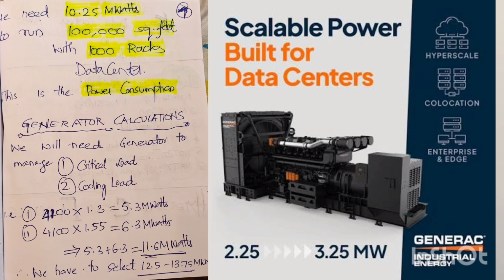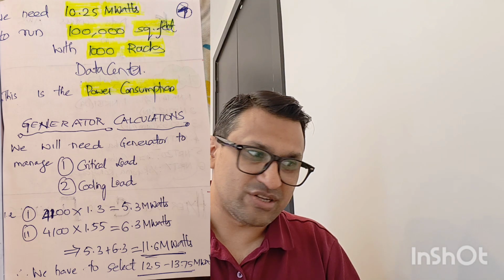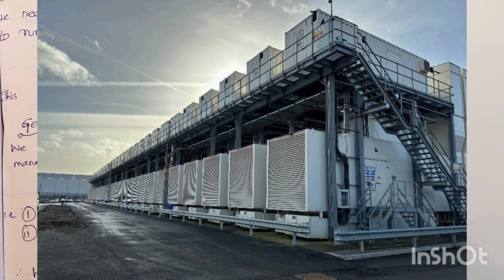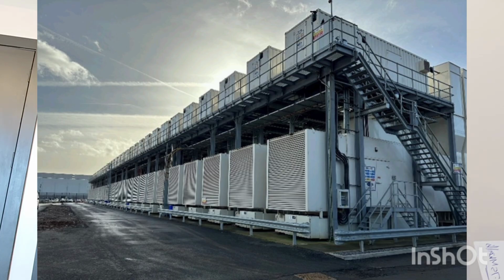Usually, you can have one generator, or you can have four generators of 4 megawatts, so that even if one fails, you have three running and still supply 12 megawatts. So we have four smaller generators providing 3 to 4 megawatts per generator. Okay, so that's the generator calculation. Remember, for the generator, you multiply the critical load by 1.3, and the cooling load by 1.55. Thank you.